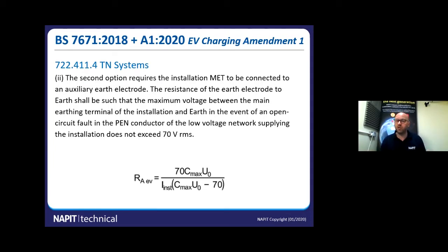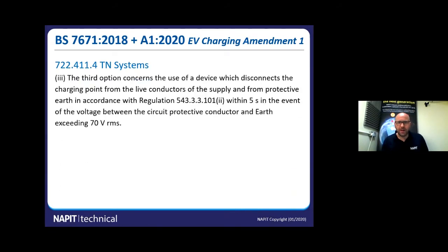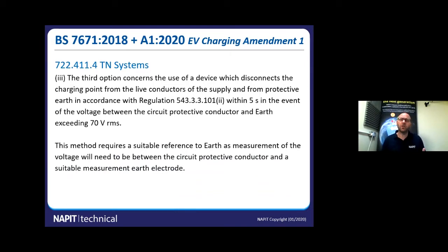Now, when we ran some demonstrations of this, when we were putting the on-site solutions together, we found that in order to achieve the 70 volts touch fault conditions, you needed an RAEV fairly low, sort of 1 or 2 ohms, so very unachievable in most cases. So option 3 concerns a device which disconnects the charge point if it sees a voltage between the CPC of the charge point and true earth. If that rises above 70 volts, it disconnects. Now, to our knowledge, these devices for indent 3 are not available, but there's nothing to stop manufacturers from producing them, so it is a third option. Out of the 3 options, it was fairly hard to comply, and therefore Amendment 1 produces some further options.